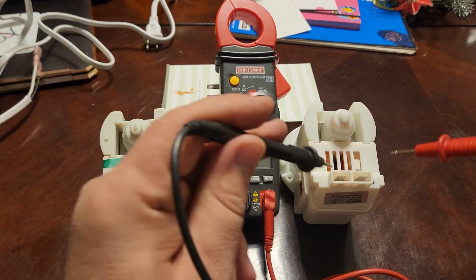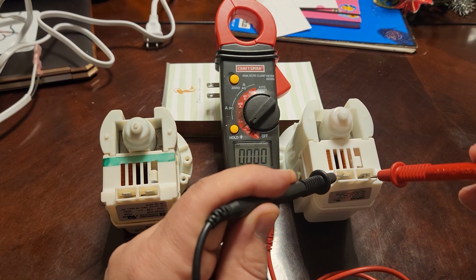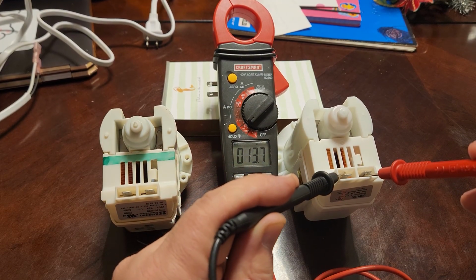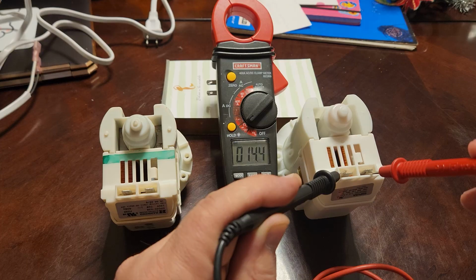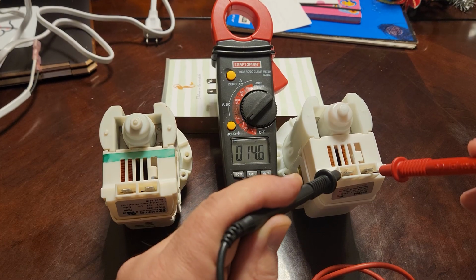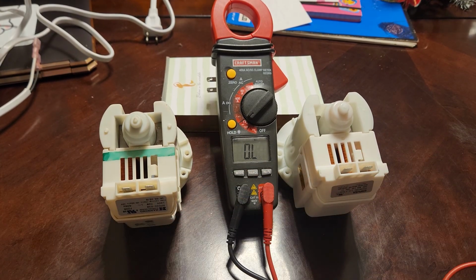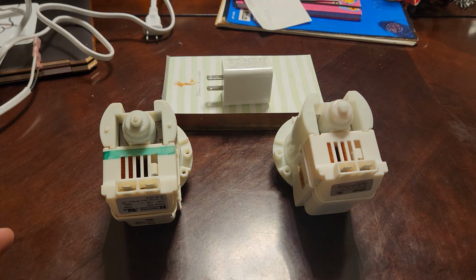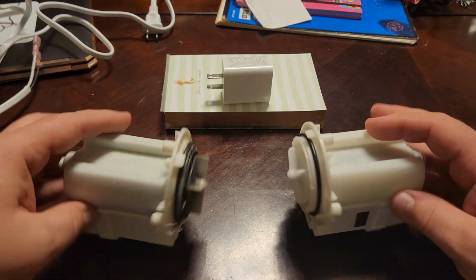The first thing we check is coil continuity. For this LG drain pump, resistance should be between 14 and 16 ohms. I put the multimeter on the terminals, and as you can see, the reading is right where it should be. So electrically, the coil looks good, but that doesn't mean the pump is healthy.